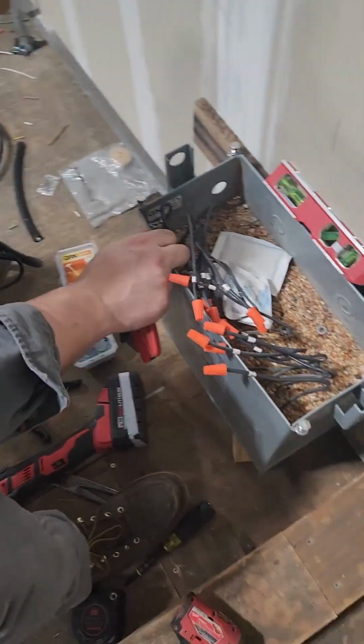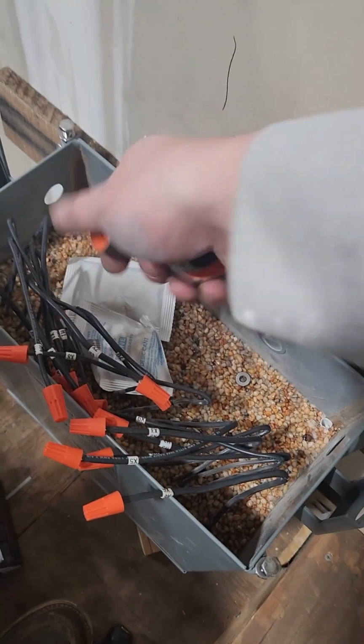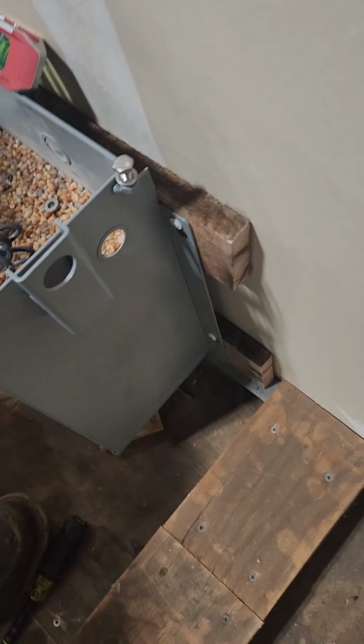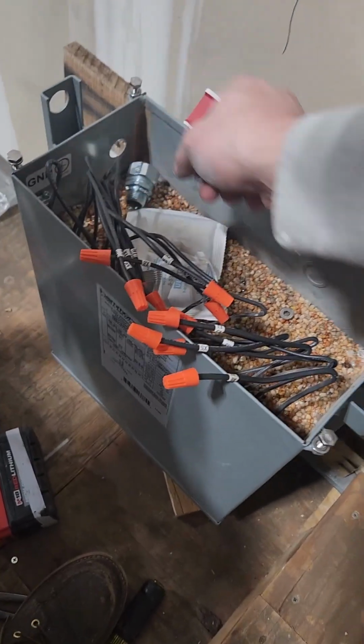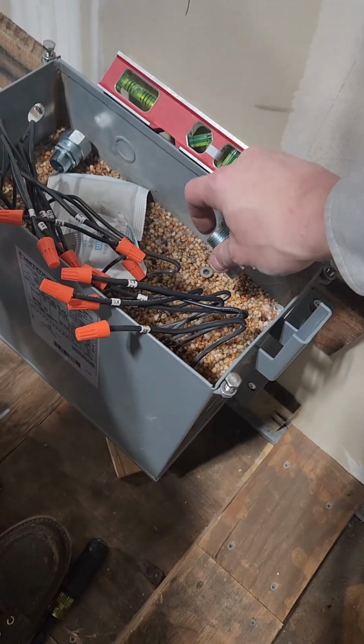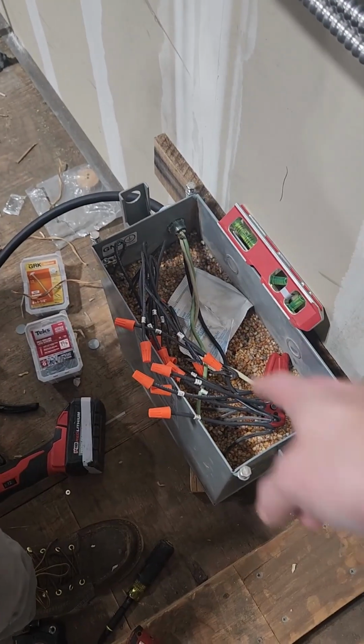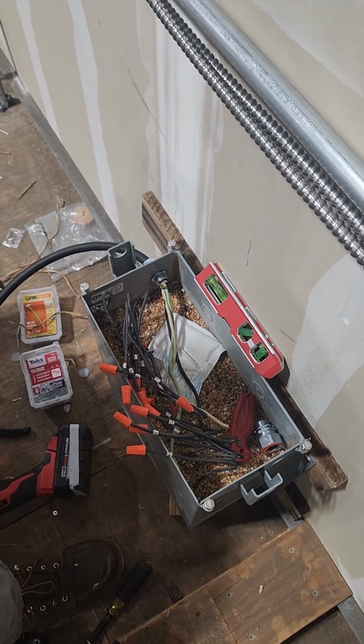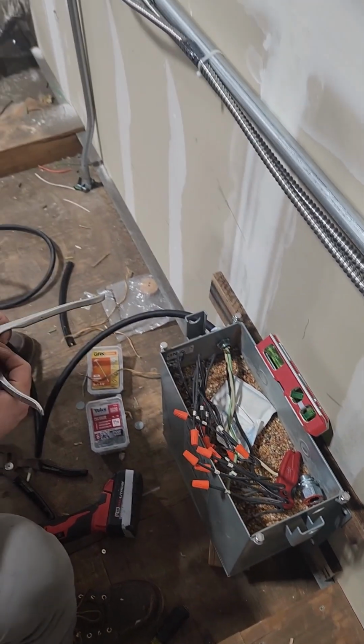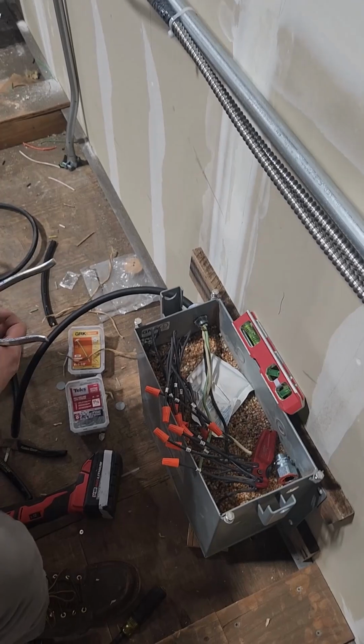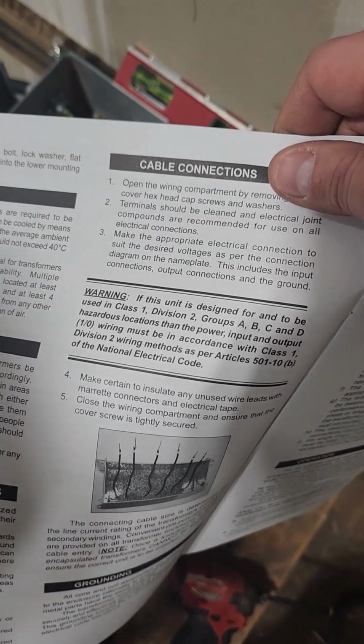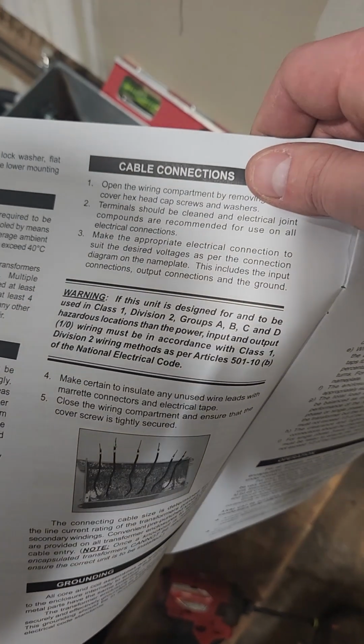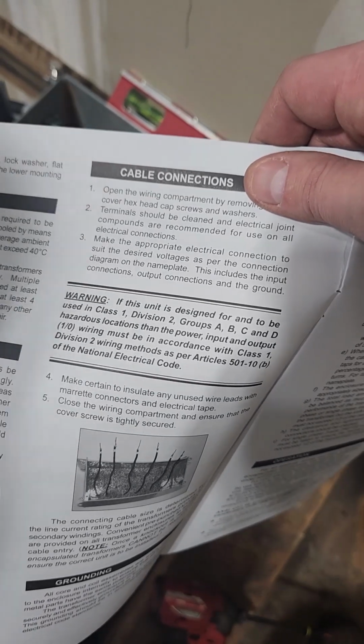So that SO cable is gonna come in through that knockout with these cord grips on both sides. 480 in over here, 240 out over here. Don't forget the instructions say to use wire compound in all the wire nuts. Yeah, I'll get right on that. Good, excellent. Does it actually say to do that? It does say that. Huh. Terminals should be cleaned and electrical joint compound is recommended for use on all electrical connections.